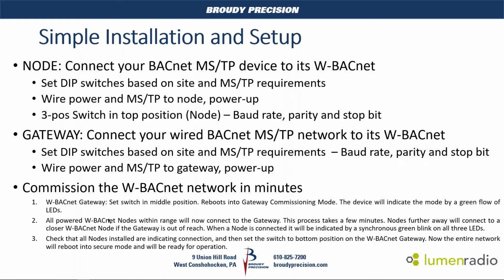And with all the W-BACnet nodes powered up and within range, they will be put into the commissioning mode and will then be built as part of the mesh, and the gateway will set that up. And when it is done, you will see the 3 green LEDs all blinking on and off on the nodes, signifying that it's done. And then once done, the third and last step is to take that 3-position switch on the gateway and set it to the bottom position. Now the entire network would reboot and placed into a secure mode, and it would be ready for operation.